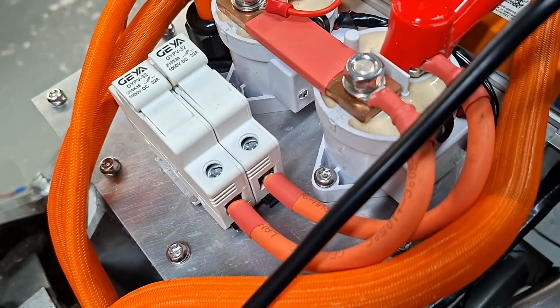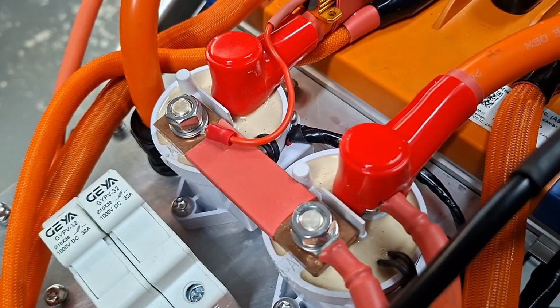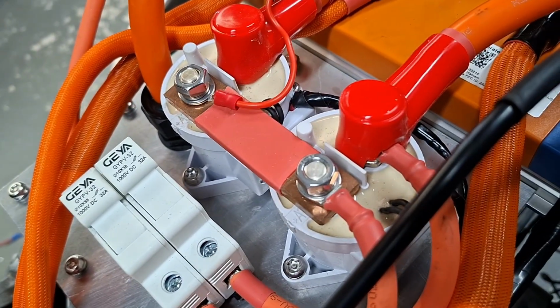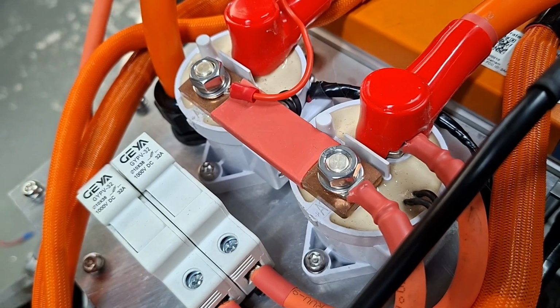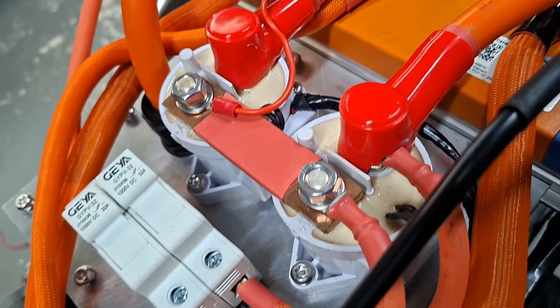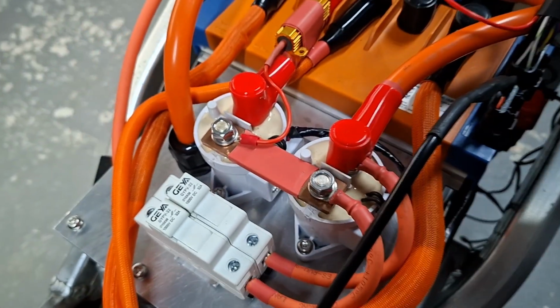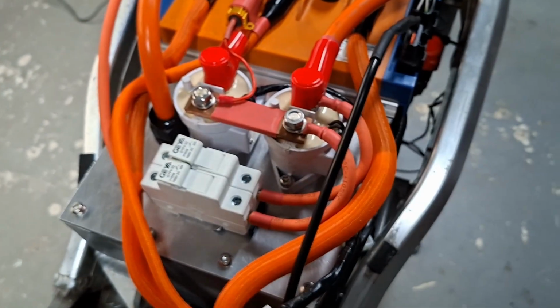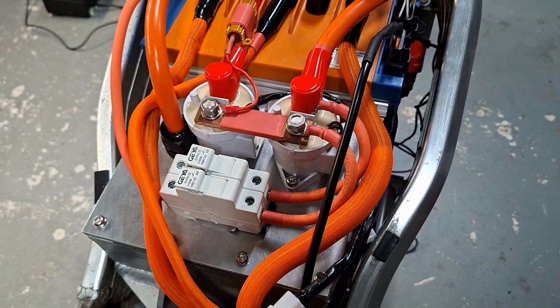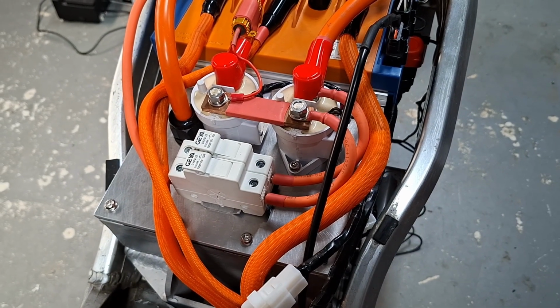So now if I turn on the kill switch, we should have contactor 1 come in, and press the start button, contactor 2 will come in. So that's all working now. The next thing we'll do is the inertia switch, we'll get that set up while we're working in this area.